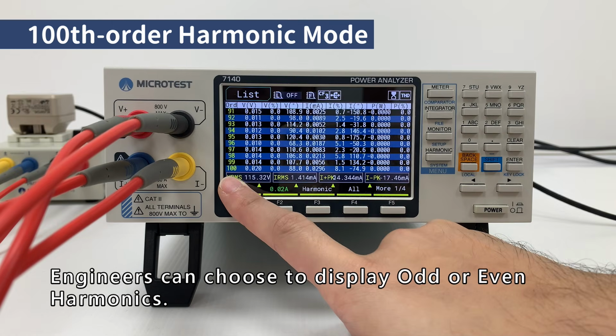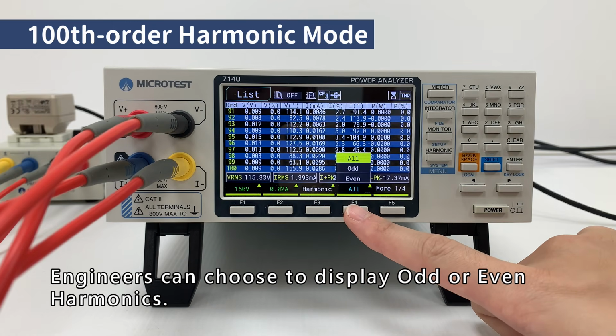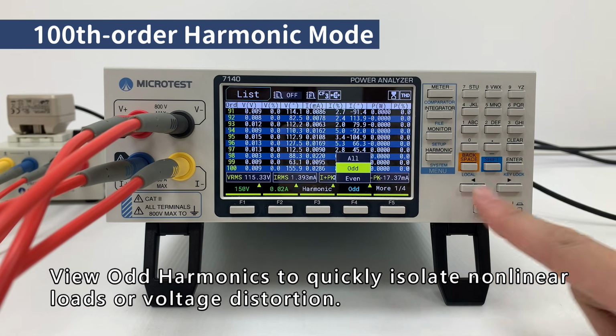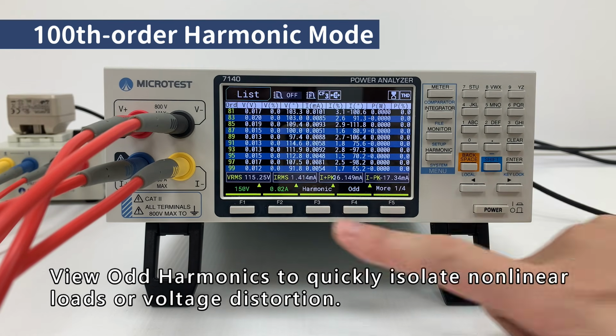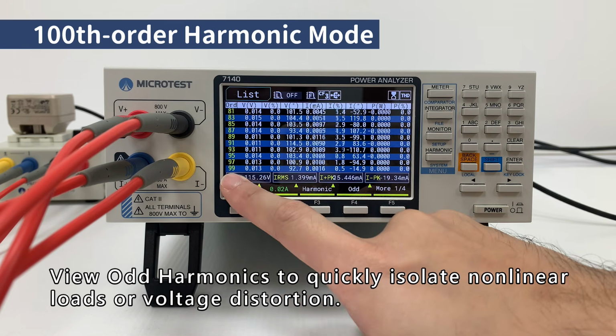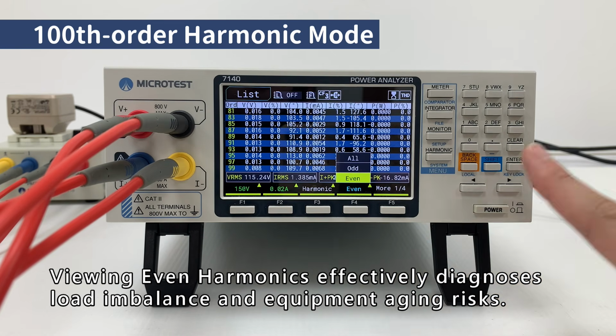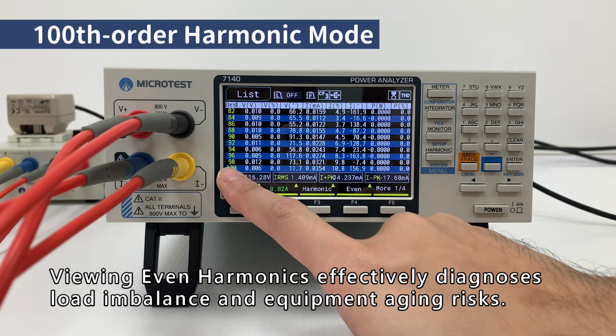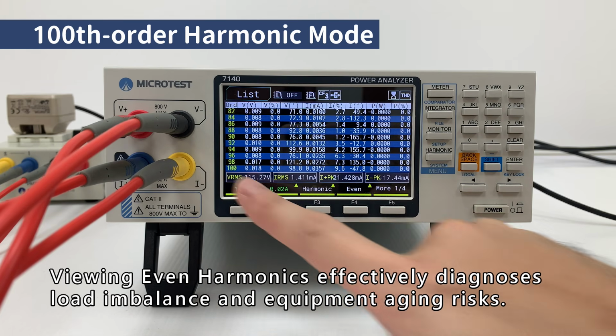In 100-order harmonic analysis mode, engineers can choose to display odd or even harmonics. Viewing odd harmonics helps quickly identify issues like nonlinear loads or voltage distortion. Viewing even harmonics helps diagnose load imbalance or aging equipment.